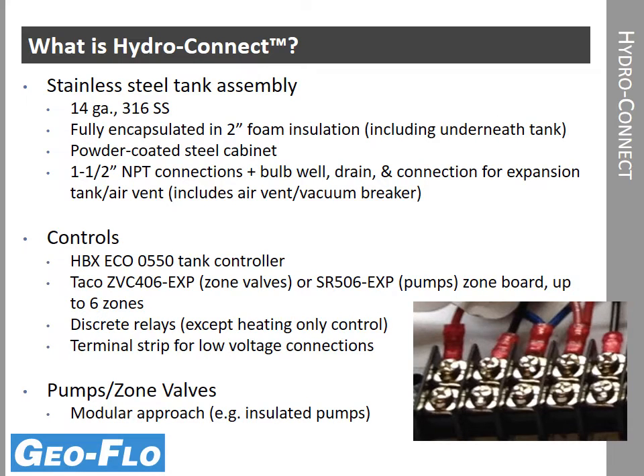We've taken all those components then with wiring harnesses and factory assembled everything into a box, and then included terminal strips for all the low voltage connections. You'll see a picture in the lower right hand corner of the terminal strips that are available on the control box. So all of the components listed here are factory wired. It's a modular approach. We can use either pumps or zone valves, and it's a matter of selecting the appropriate number and size of pumps or zone valves accordingly.